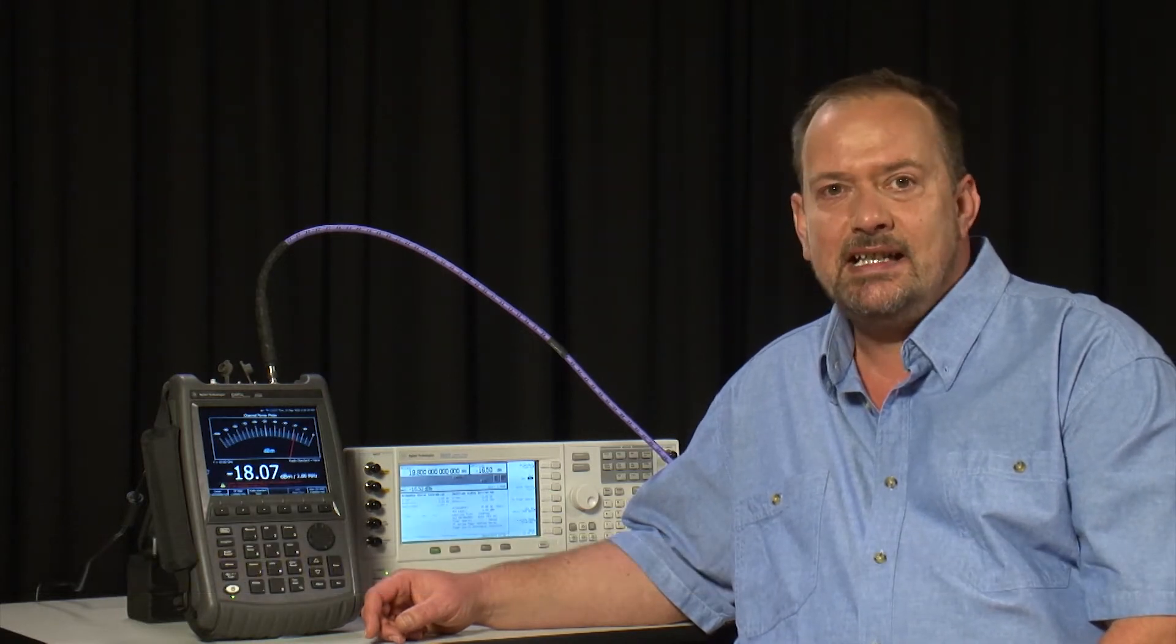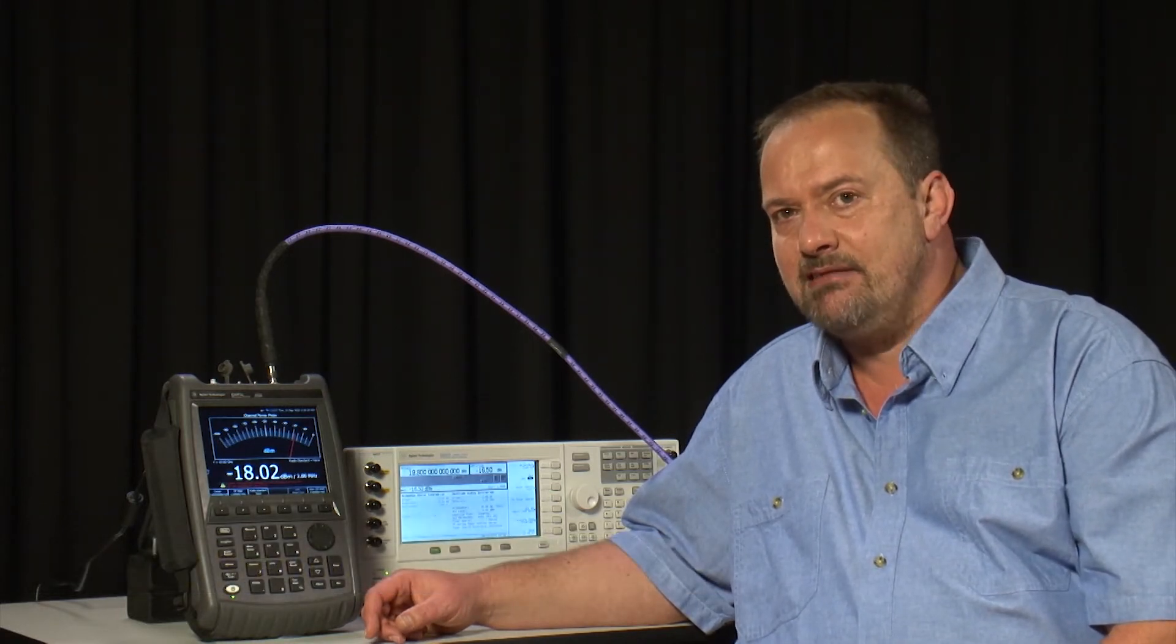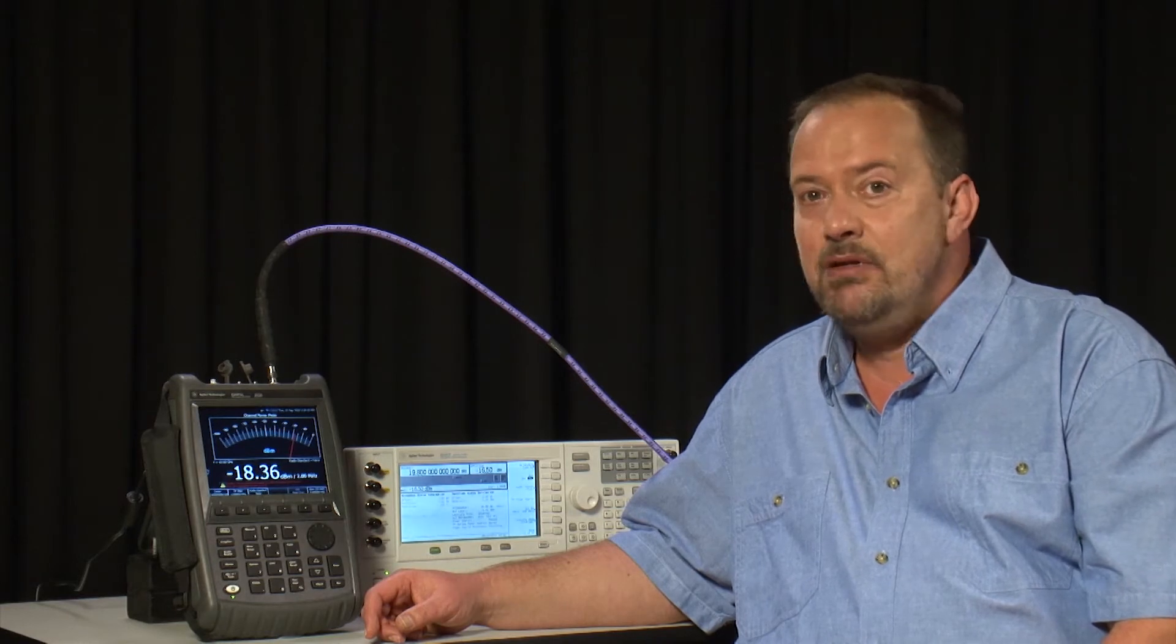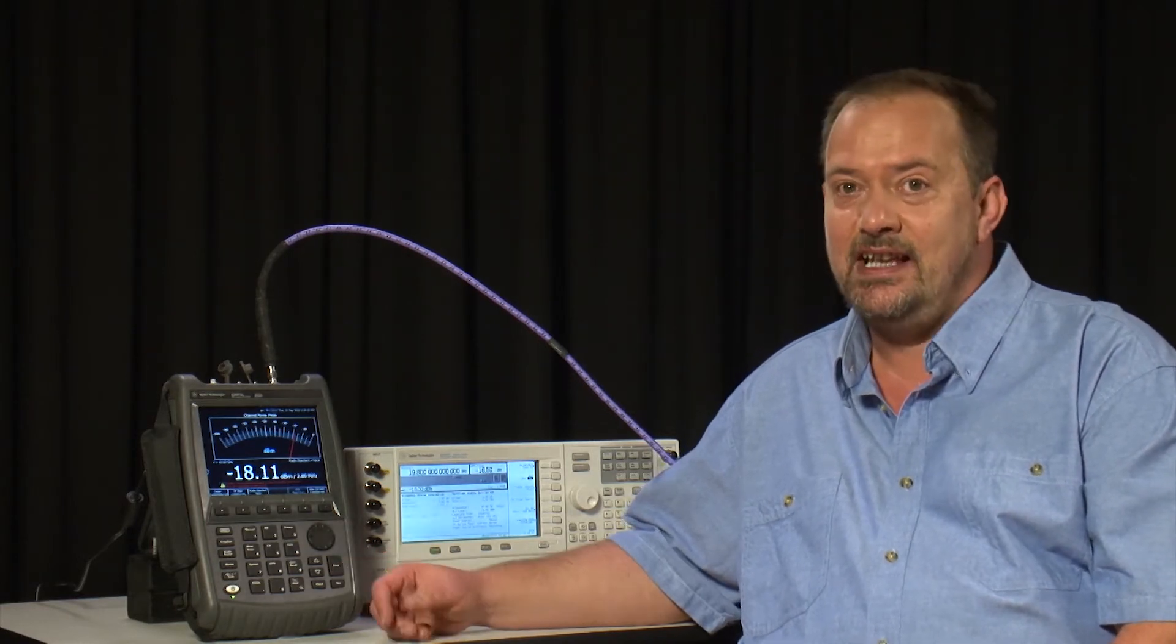The built-in channel power meter option on the FieldFox is very simple but incredibly useful, as it makes amplitude measurements with comparable accuracy to a real power meter, but without the need for an external power sensor.